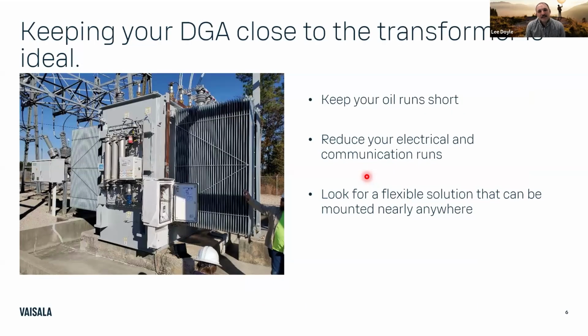Yeah, thanks, Senja. To build off of that, what I found to be really important is to try and keep the monitor as close to the transformer as possible. So having the flexibility in your monitor that you could possibly mount it to the transformer, or if you have some sort of custom mounting solution, if it can adapt to that, is really ideal. And the reason you want to do that is obviously you can reduce your costs, maybe not significantly, but metals in particular are going up in cost, so you can reduce your cost there.